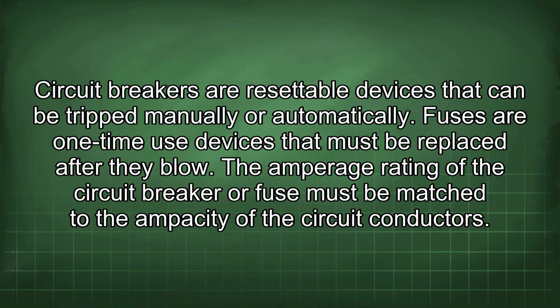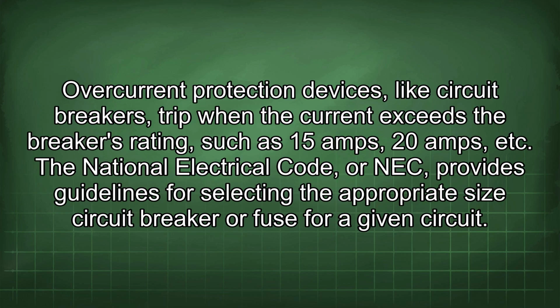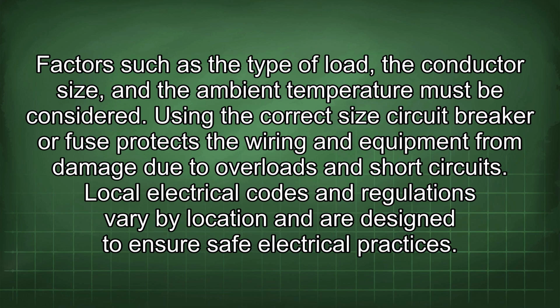Circuit breakers are resettable devices that can be tripped manually or automatically. Fuses are one-time use devices that must be replaced after they blow. The amperage rating of the circuit breaker or fuse must be matched to the ampacity of the circuit conductors. Overcurrent protection devices, like circuit breakers, trip when the current exceeds the breaker's rating, such as 15 amps, 20 amps, etc. The National Electrical Code, or NEC, provides guidelines for selecting the appropriate size circuit breaker or fuse for a given circuit. Factors such as the type of load, the conductor size, and the ambient temperature must be considered. Using the correct size circuit breaker or fuse protects the wiring and equipment from damage due to overloads and short circuits.